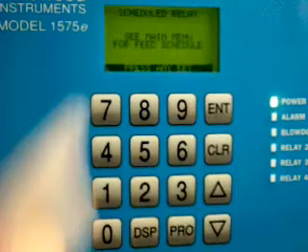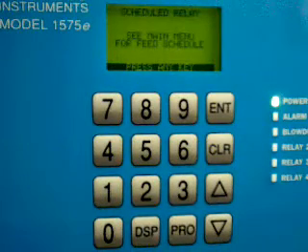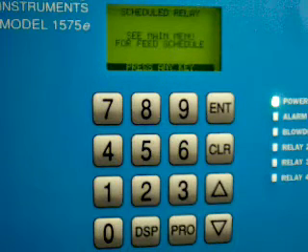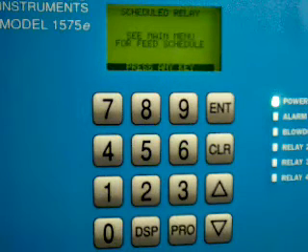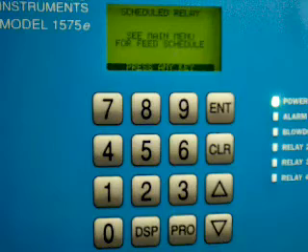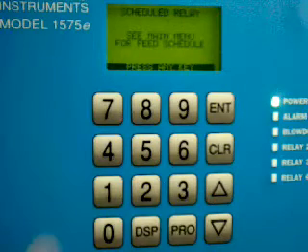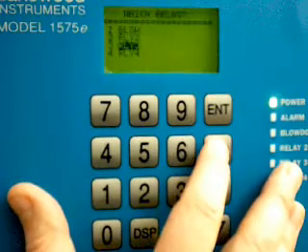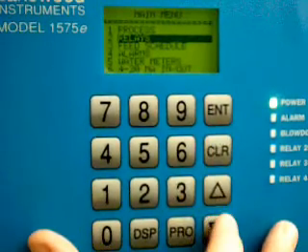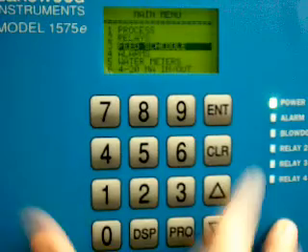We're going to turn this on as a feed schedule relay. So I will go to feed schedule, which is item six. Press enter. Now the instruction says, see main menu for feed schedule. What I've done is tell the relay it's a feed schedule relay, or a time-based relay, but I need to go now into the schedule itself and tell it how to act within that schedule.